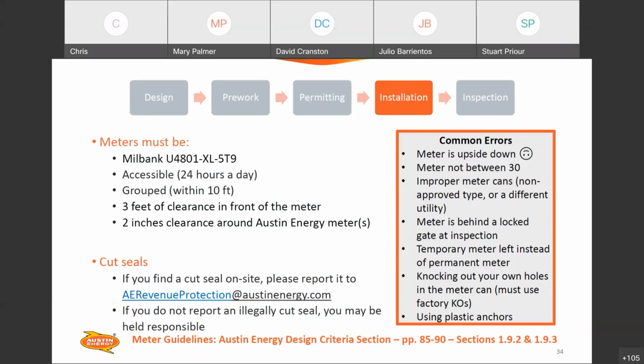Some common errors in metering are that the meter is upside down or it's wired incorrectly. The solar output circuit is always going to be on the line side of that meter, so that meter spins in the proper direction. Pay close attention to that. The meter is not between 30, that should say 30 inches to 72 inches. And that's to the center of the meter where you can actually read the numbers, 30 inches on the low side, so 2.5 feet, and then 6 feet on the high side. Keep it within that range.